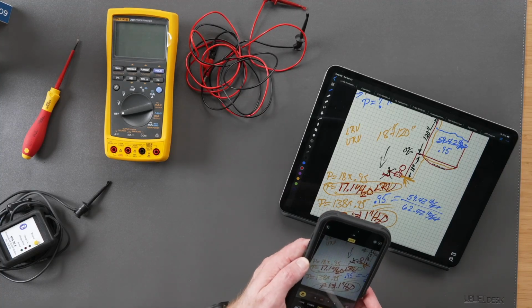Let's catch a quick snapshot of that, because that's what we need to go in here and program into this transmitter we've got sitting on a bench. We want to take it out to the field pre-configured, stick it onto the tank, and it should work. If we've made good measurements in the field and done our calculations correctly, there should be no reason this shouldn't go into the field almost seamlessly.